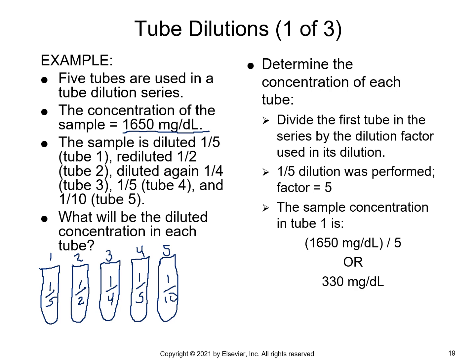Let's say that our first dilution is a 1 in 5 dilution on tube number 1. Tube 1 has 1 part sample volume, and the bottom number will be the diluent volume. After we make tube 1 and run it, let's say the analyzer still gives us a result outside of the range. So rather than making a new one, we take that tube and dilute it again.